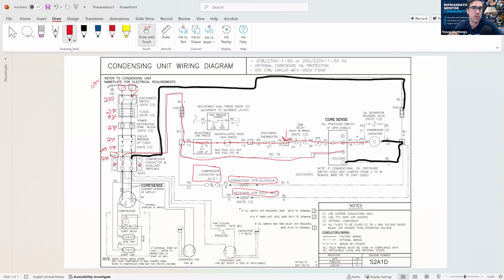It's like a switch. When you go across a switch and that switch is closed, just say we go right here on the high pressure switch. You put your probe right there upstream and put it downstream. If that switch has voltage going through it and you put it on one side and the other side, you will get 0 volts. If that switch is open, you will get 230 volts. On this one here, you will get 115 volts because we don't have any power coming through the contactor.